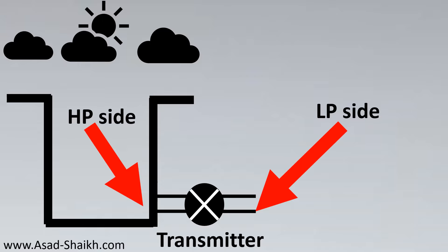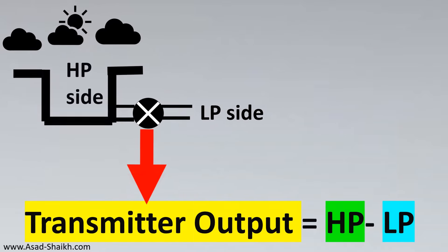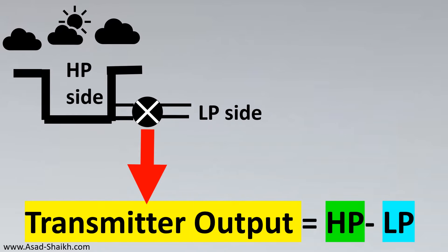This configuration that we are going to use is called the dry leg configuration. The transmitter output is always the difference between the HP side and the LP side — thus the name differential pressure transmitter. It gives the difference between the HP side and the LP side.